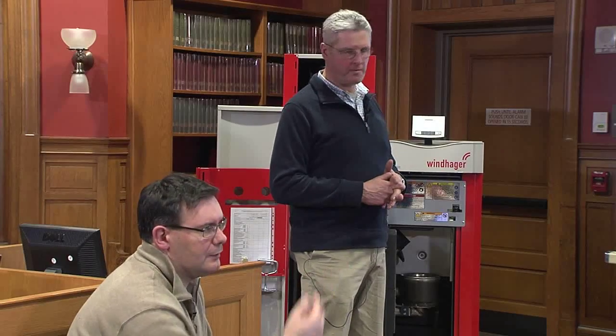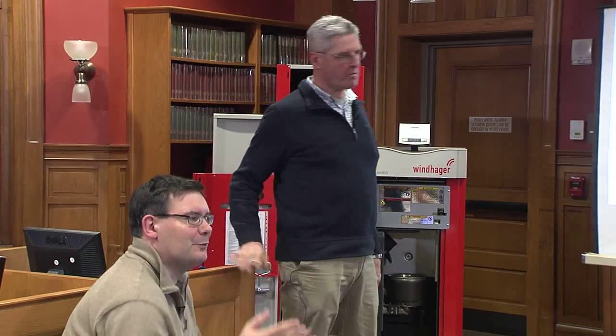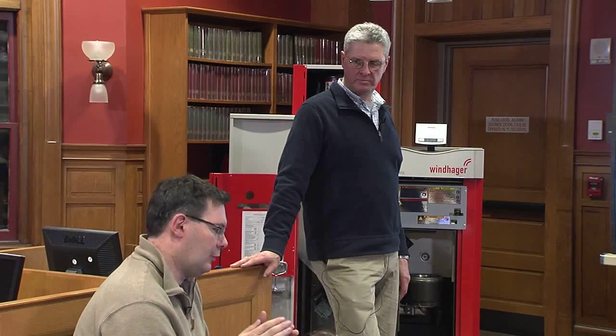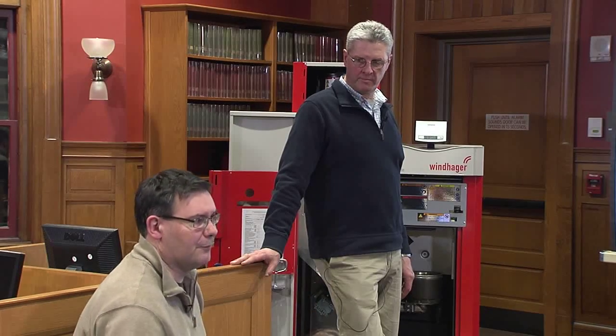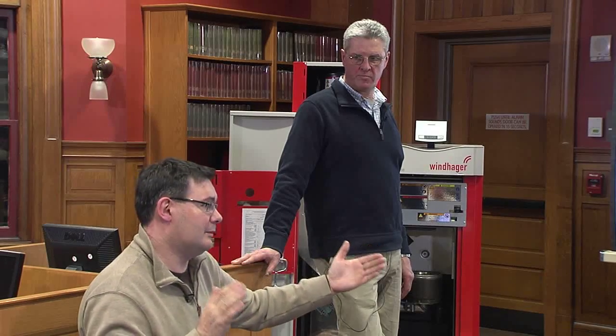Like for instance, Mark's unit we were tweaking the last 2 weeks. We put in a 51,000 BTU. That's how we started. But even in the cold snap, it's too big. We turned it down now. With a biomass appliance, the goal is to have it run as long as possible, like 2-3 hours if possible at a time. That's when it becomes the most efficient. You don't want to have it switch on for 15 minutes. It takes 10 minutes to get the fire established. So the longer you can let it run, the more efficient, and also the less wear and tear on the moving parts.